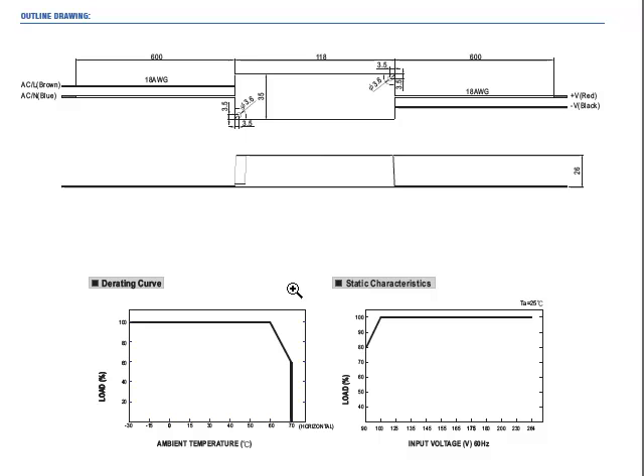If you download the specification, you'll see a complete envelope drawing. Here we have the derating curve, which shows that you can get full load operation to about 60 degrees Celsius and derate about 5% per degree C down to 50% maximum power at 70 degrees C.